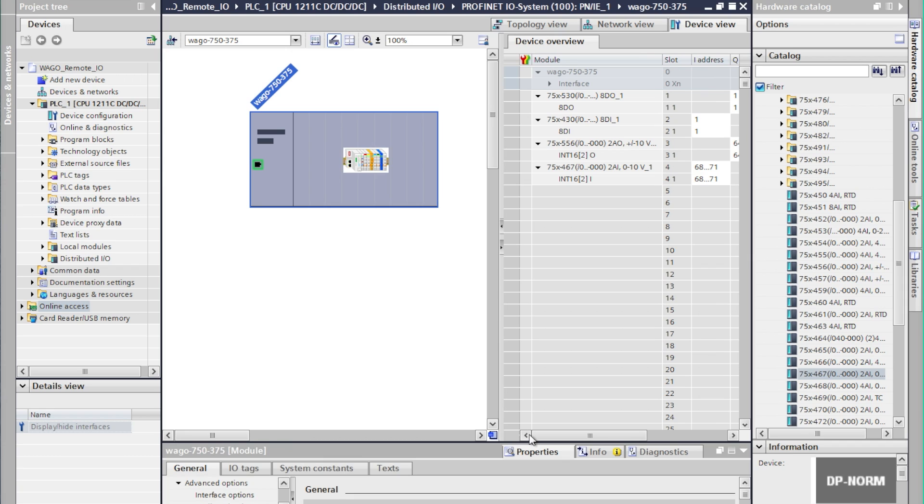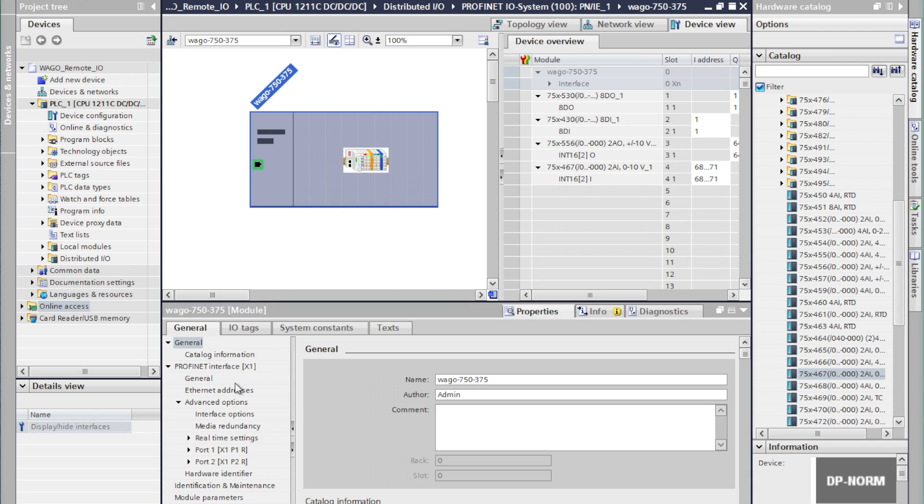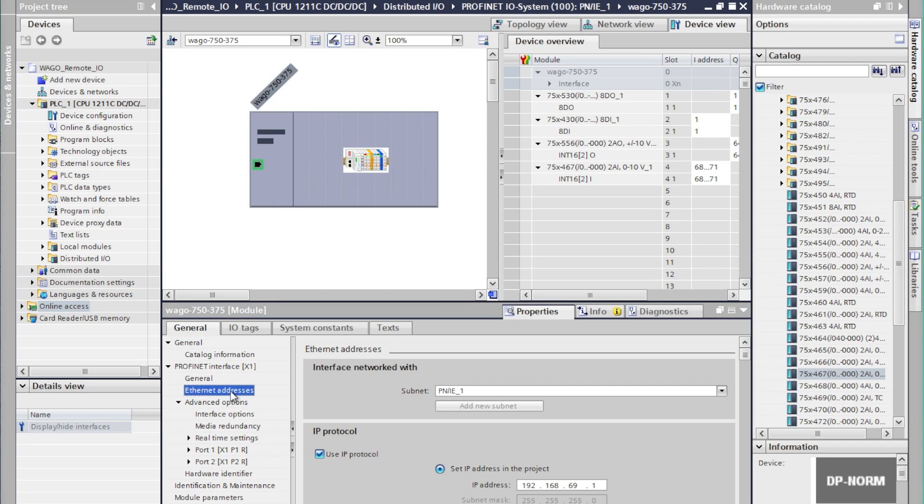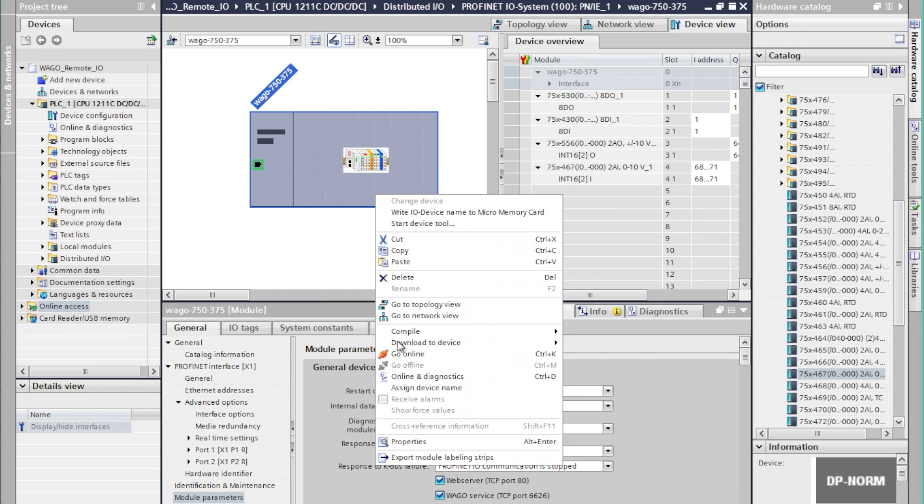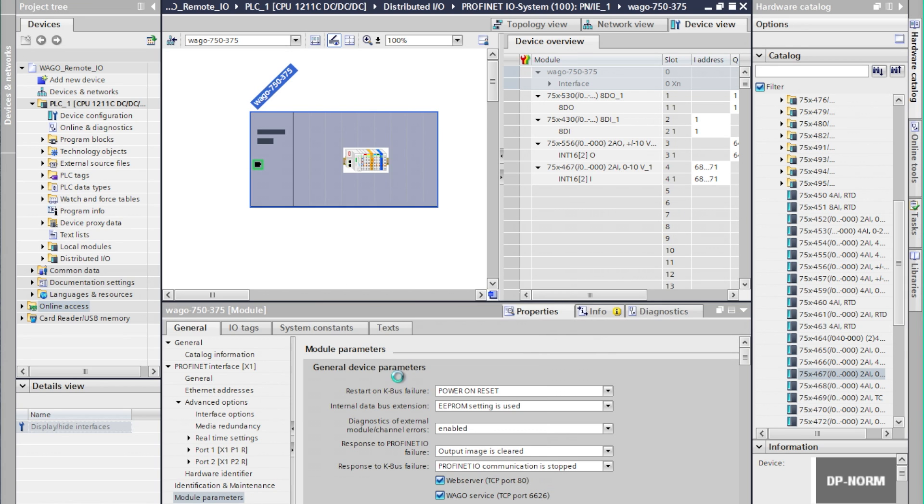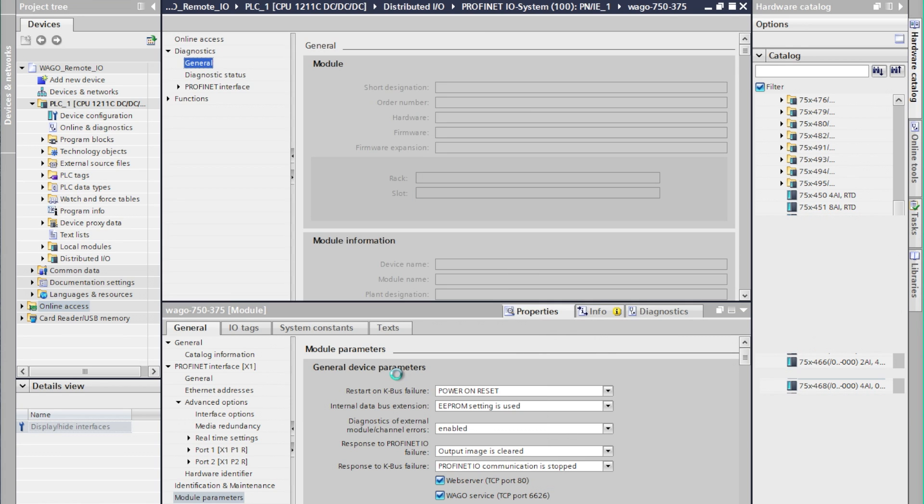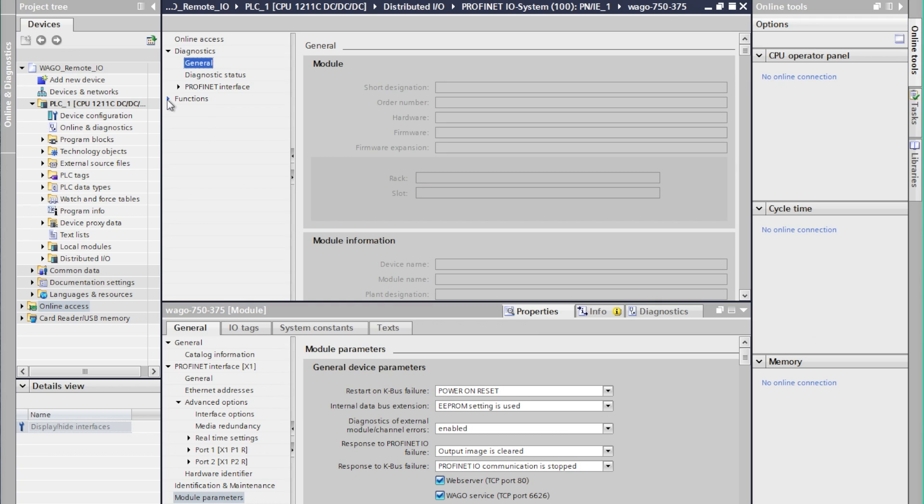We're going to go through the same steps for the PROFINET coupler as well. One added step here though, once we've assigned the IP address we'll also want to go in and enable port 80 which is an onboard web manager that allows us to do some diagnostic checking and some configuration over a web browser.